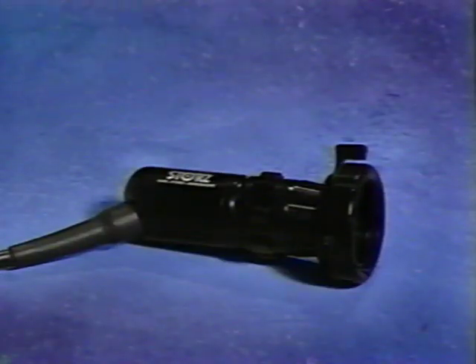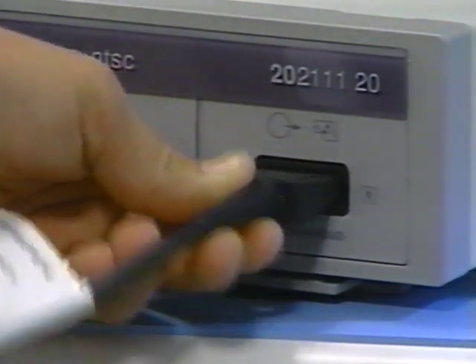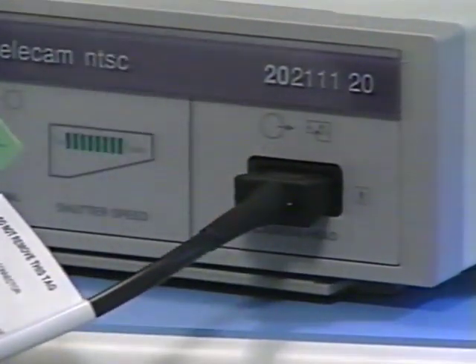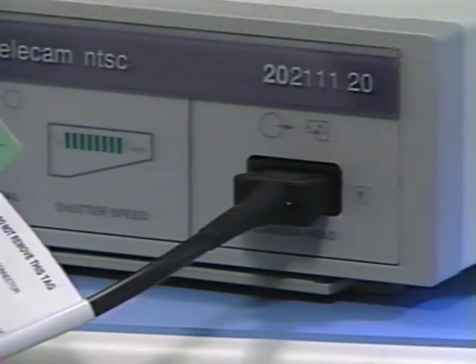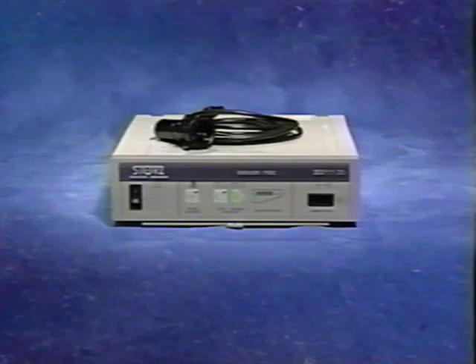A camera head attaches directly to the endoscope. The optics in the camera head focus the image as seen through the endoscope onto the camera's sensor. The camera head adapter magnifies the image for monitor viewing. The optical information is carried by a camera cable to the camera control unit or CCU, where it's processed and sent to the monitor. The CCU contains all electronic processing of the video information and control of functions like auto white balancing and auto exposure.